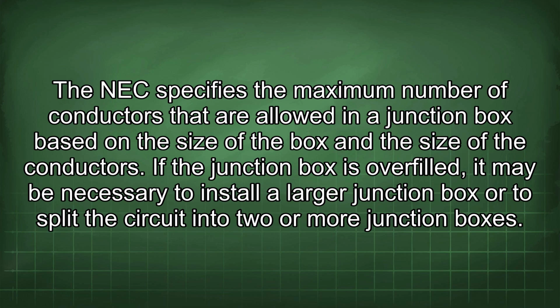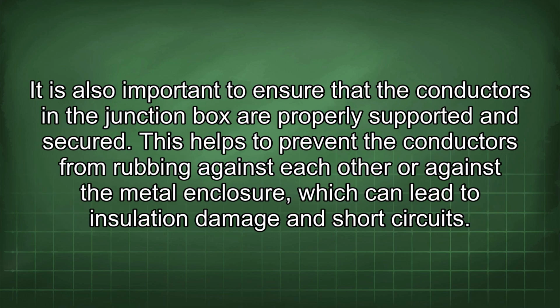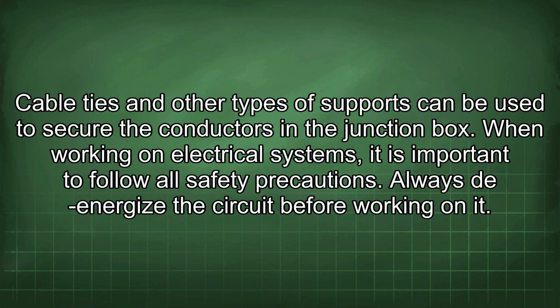If the junction box is overfilled, it may be necessary to install a larger junction box or to split the circuit into 2 or more junction boxes. It is also important to ensure that the conductors in the junction box are properly supported and secured. This helps to prevent the conductors from rubbing against each other or against the metal enclosure, which can lead to insulation damage and short circuits. Cable ties and other types of supports can be used to secure the conductors in the junction box.